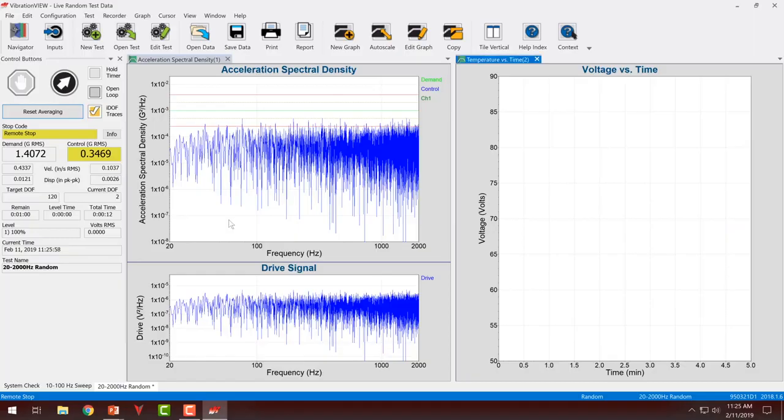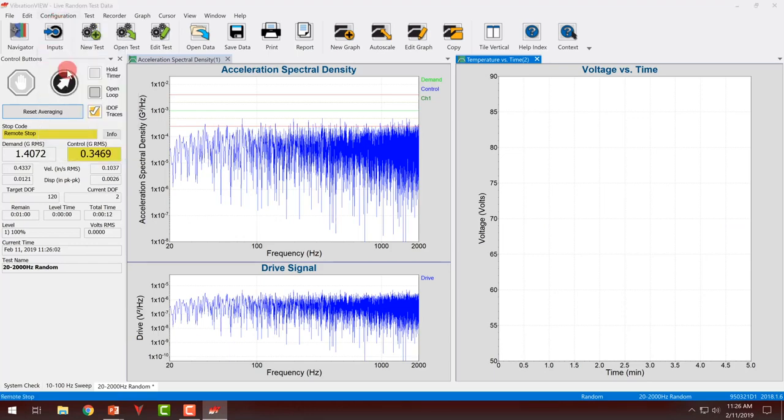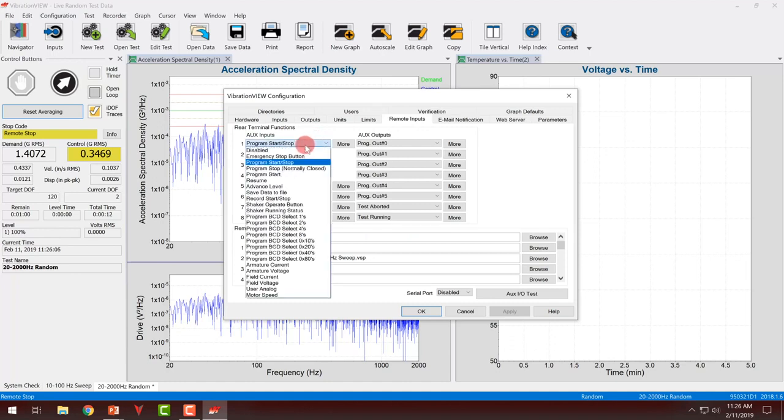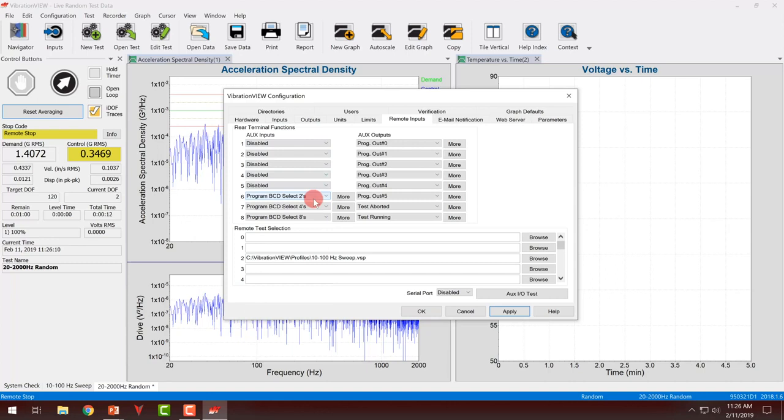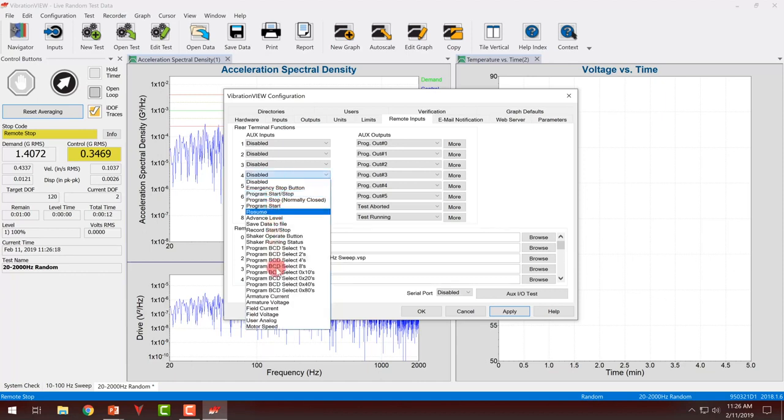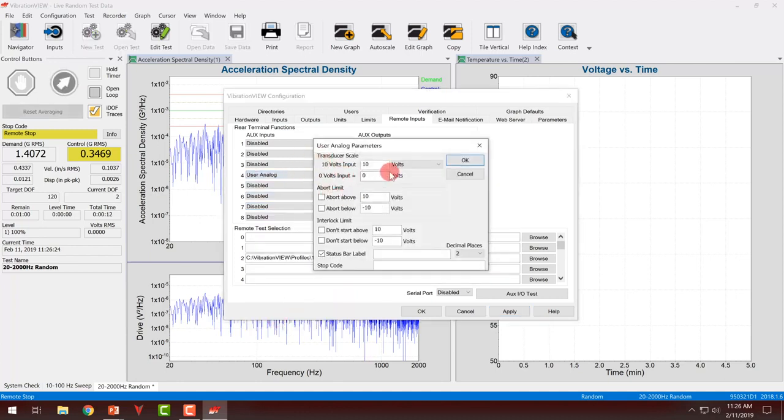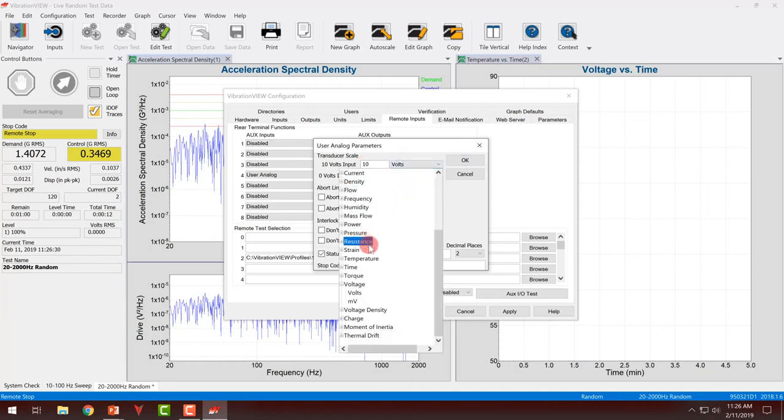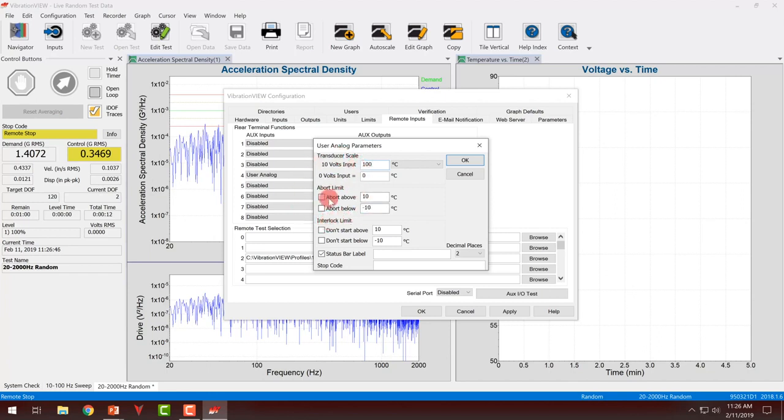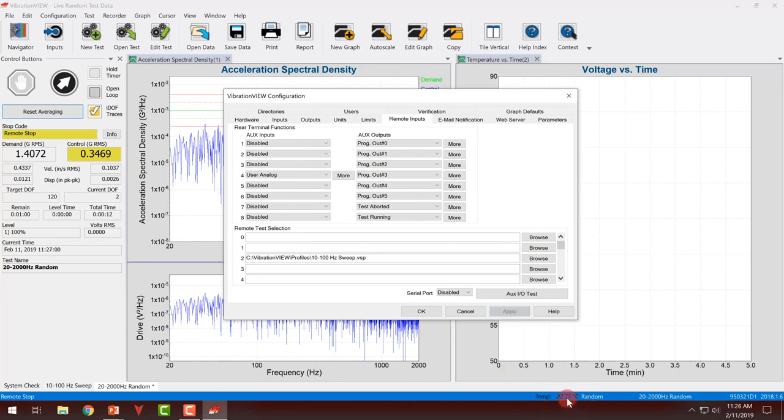If we take a look at that in vibration view, go again to configuration, remote inputs, reset all of this. In this case, my analog signal is connected to channel four, so I can just do user analog. When I click more, it allows me to define my units on a 0 to 10 volt scale. If we were talking temperature, I could pick temperature, degree C, and say that 0 is 0 and this is 100. I can set my abort and interlock limits if I choose to. I can also put in a status bar label.